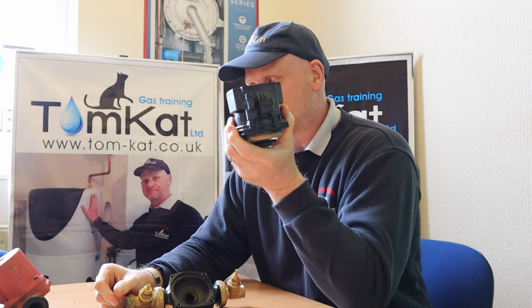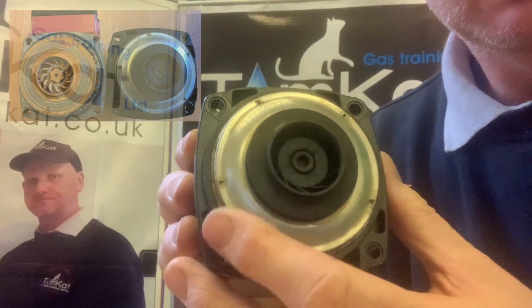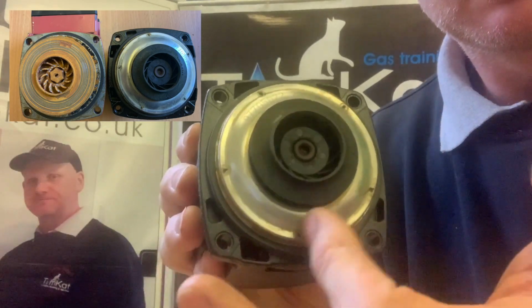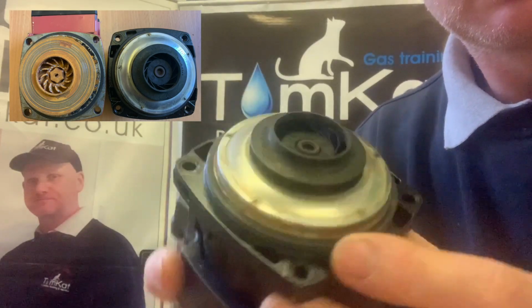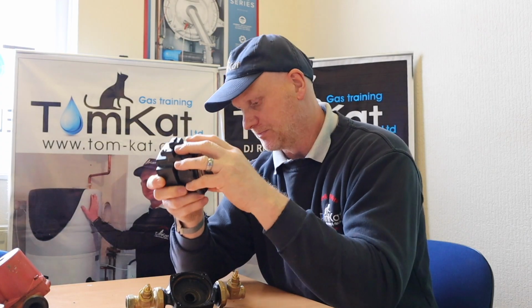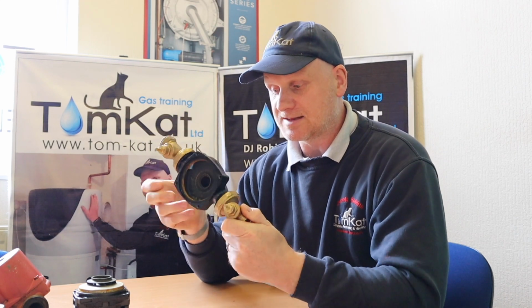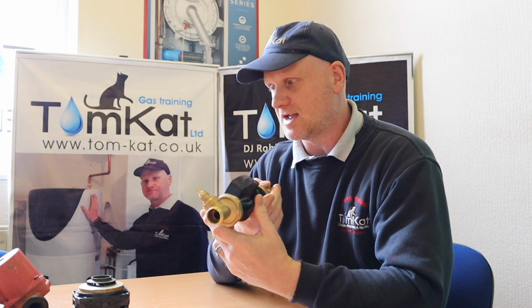This is a lot lighter than the old heads. That's the first thing you can see. And look at the size of the impeller. It's tiny. Tiny little impeller now. That's probably so it can fit in most boilers, most combi boilers. So the body looks exactly the same. It's still laid out the same. So this head, let me go back and get the old body.